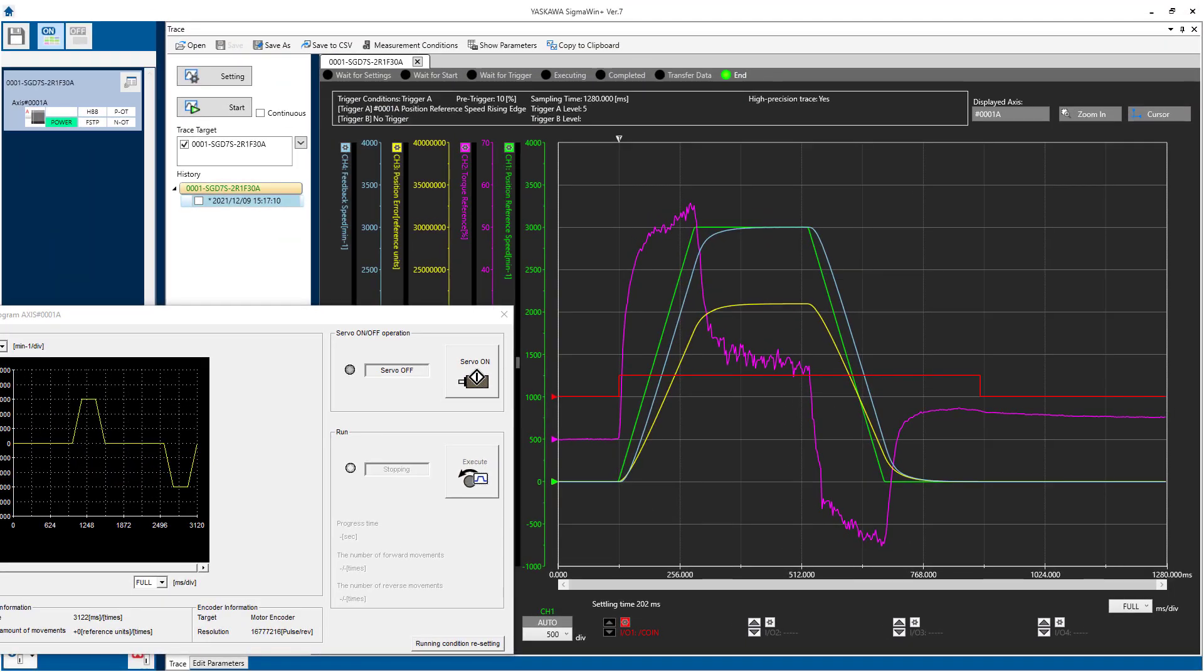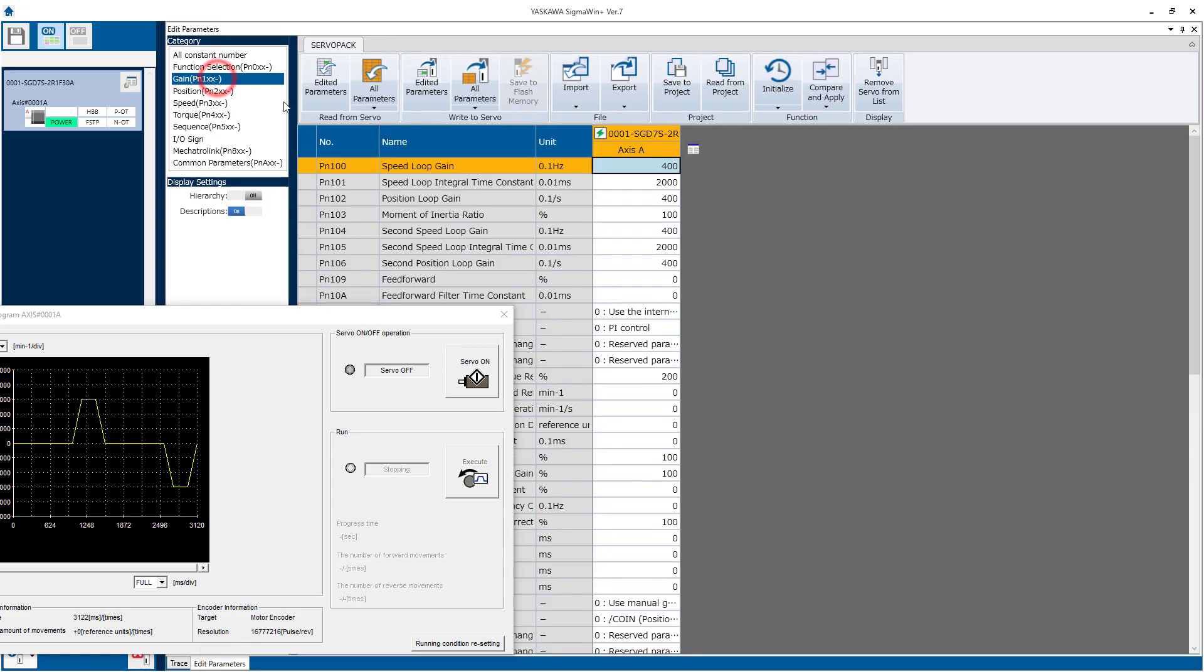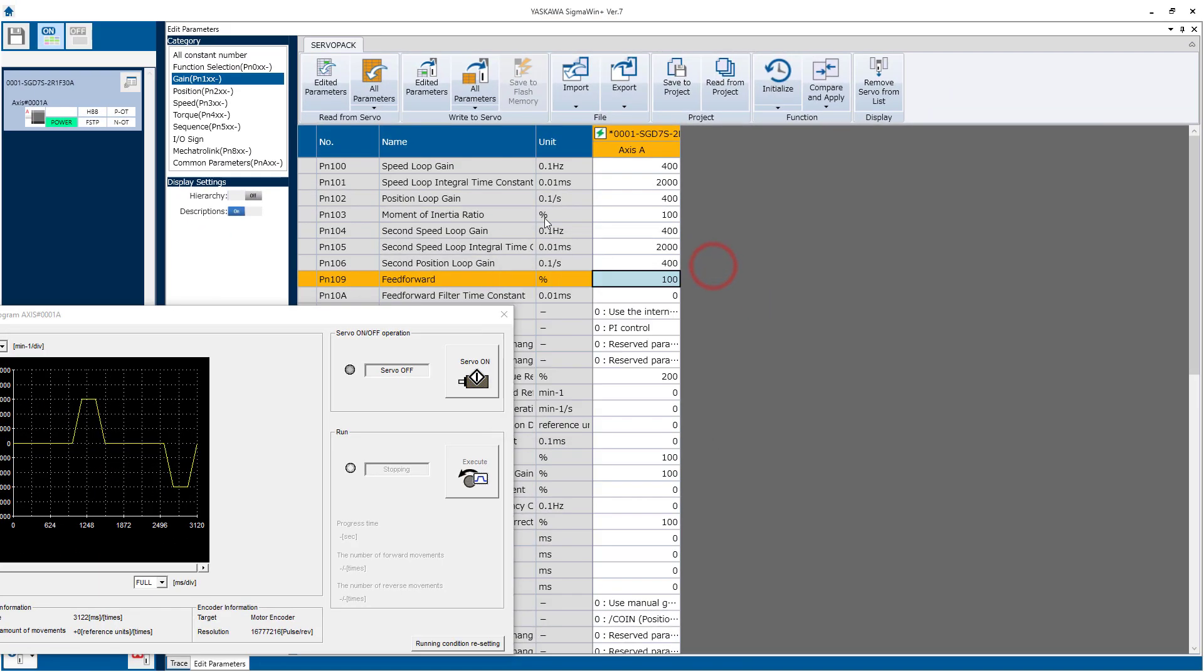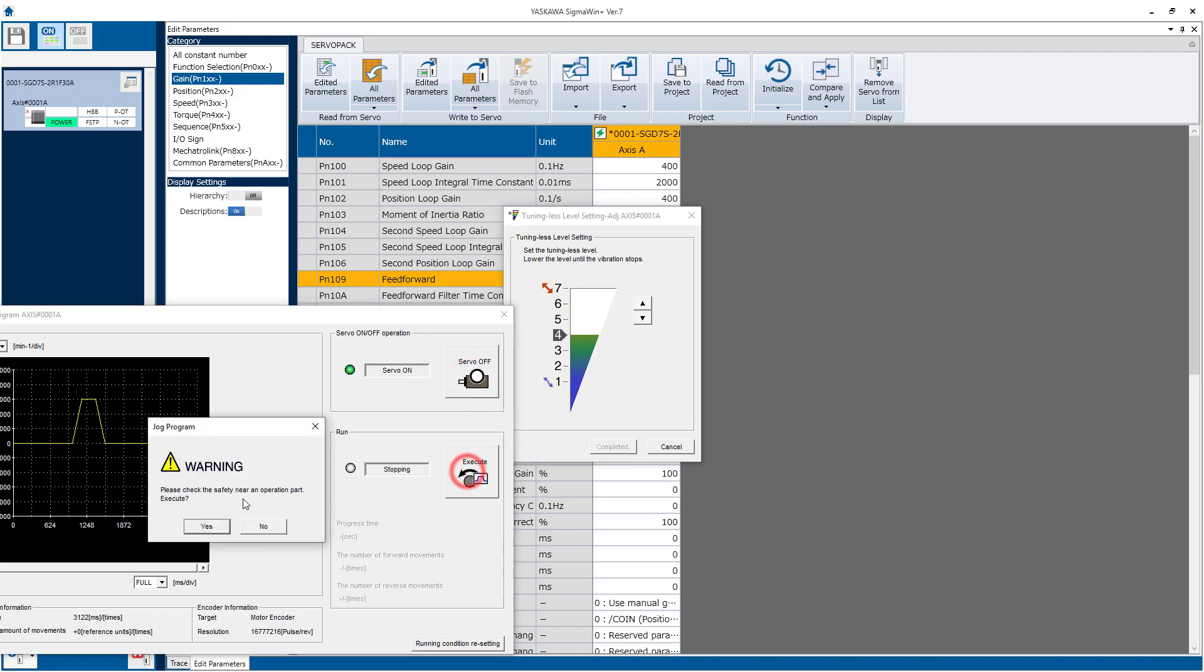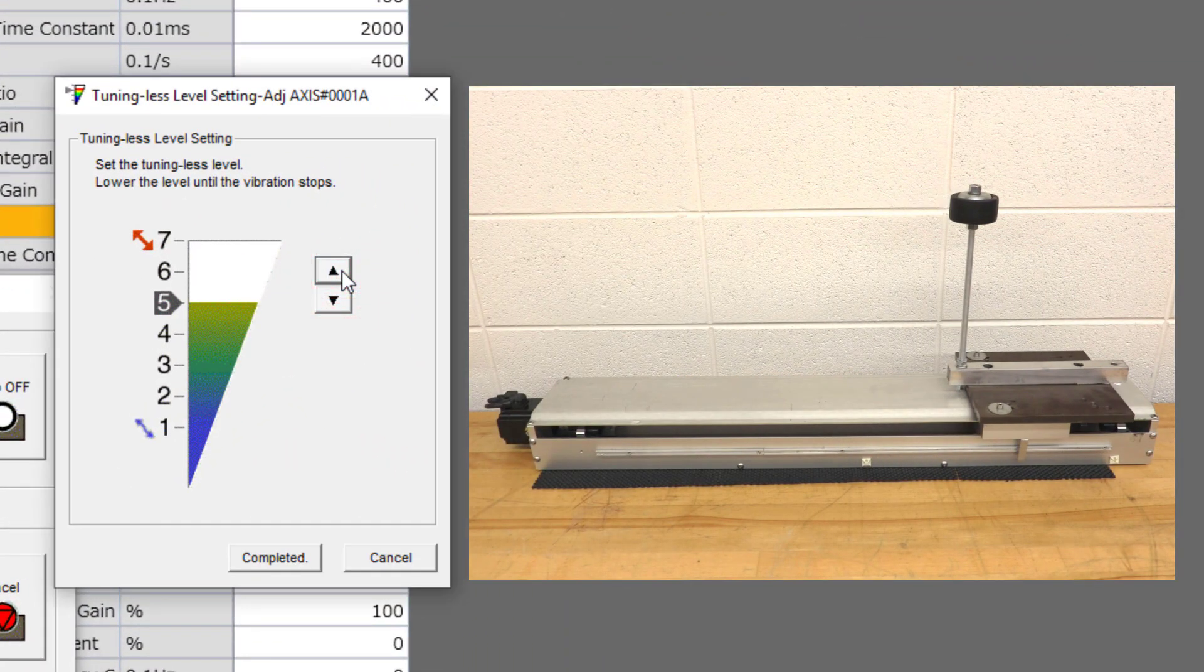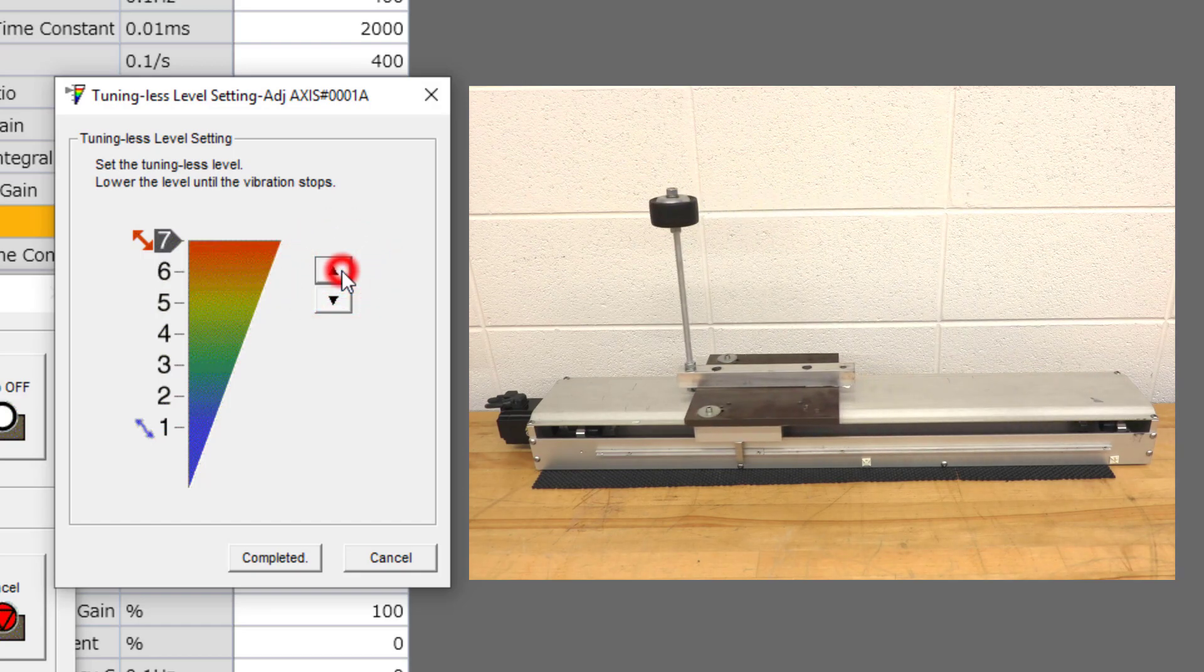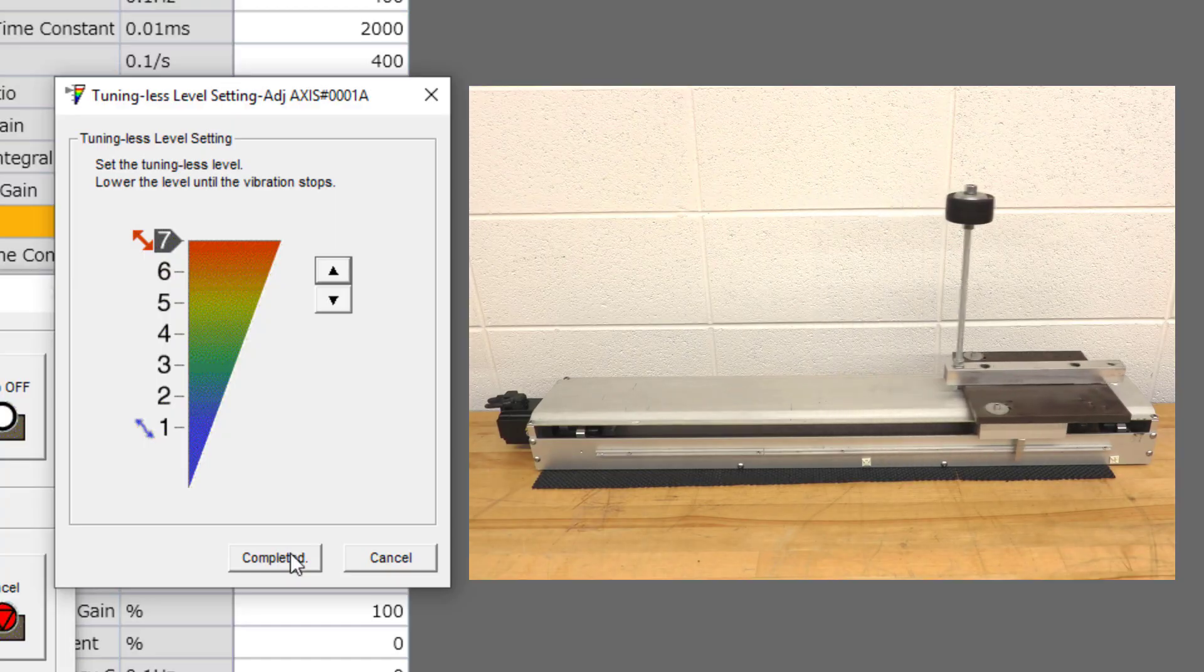The quick and easy way to lower the position error is to just keep on using the Adaptive Tuningless Mode, which is on by default. But maximize PN109, Feed Forward, to 100%, I'll write that. And then raise the Tuningless Response Level setting as high as possible without producing any noise. So you want to do this with the motor running, and just gradually increase. If there's no noise, then you can leave it at the maximum, like this.